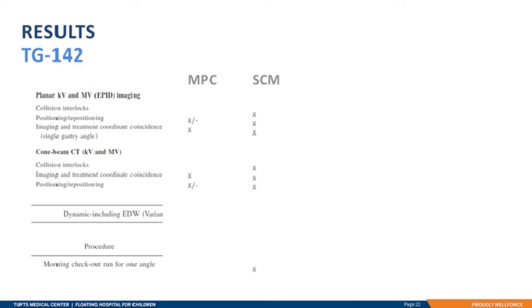For the remaining TG-142 tests, Machine Performance Check reports on the positioning of the imaging unit as well as the imaging and treatment isocenter coincidence for all imaging modalities. However, it does not look at repositioning or collision interlocks. It also does not assess the EDW. SunCHECK Machine does allow for data collection for these tests. They are part of the TG-142 template, but the results do need to be entered manually.